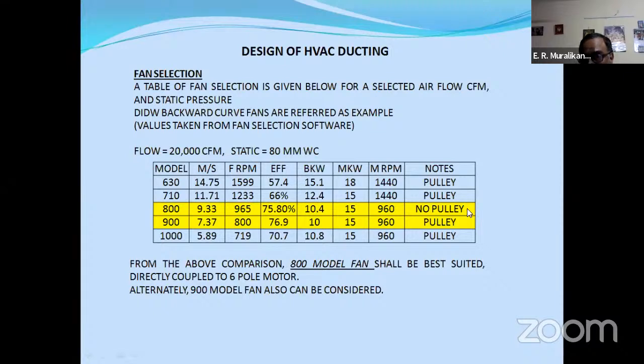Okay. Now 900 also can be preferred, because the efficiency is not that much different. But here you have to use a pulley. So when you put a pulley, this motor RPM is say 960, and here the fan RPM is 800. You can put a small pulley and reduce it.